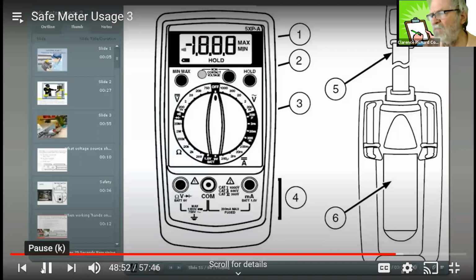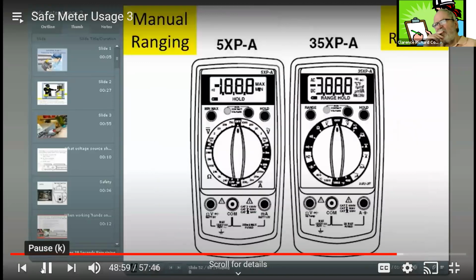What we got here? Safety problem when someone is checking a circuit for no voltage before they physically touch it. Meters are sometimes called multimeters because they can multitask. They can be used to measure voltage or current or resistance, etc. The meter on the right is an auto ranging meter with a simple function selector switch. It has a busy looking display that displays the value as well as the function in engineering units. On the left is a manual ranging meter and has a busier function range switch that adjusts for range as well as selecting the function.